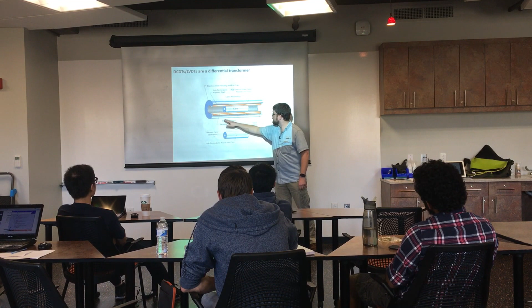Let's say we're in the center. The primary winding is fed an AC signal, generally a sine wave, around 10 to 15 kilohertz for most transducers. That also limits how fast the sensor can respond, its response time. With the core in the center, we generate an alternating magnetic field with the primary winding, and the core, being very ferrous, couples that field equally to the secondary windings when exactly centered.